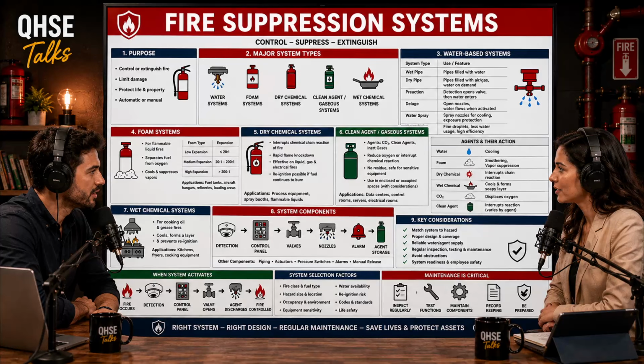Okay, so knowing what puts out a fire is step one. But before we can deploy an agent, the facility has to actually detect the fire. The sources mention that fire protection engineering is fundamentally a war against time. We have heat detectors, smoke detectors, flame detectors. How does this sensory network actually function? Well, you have to match the sensor to the expected hazard profile of the room. In the vast majority of standard commercial fires, there's a significant smoldering phase that produces smoke long before there's enough thermal energy to trigger a heat detector. So smoke detectors are your primary early warning system. Yes. And there are two main types of smoke detectors that the exams focus on: ionization and photoelectric.